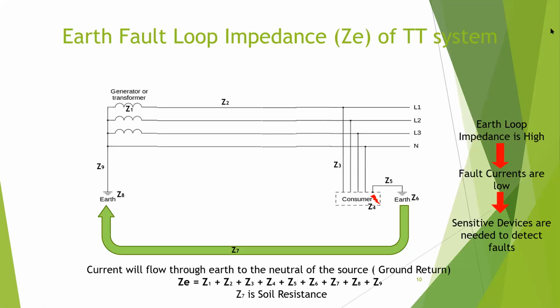Now we are going to define the earth loop impedance of the TT system. This is one of the most important things you should know. Assume you have a fault in your system. When that fault occurs, there's a path for the current to flow. The impedance or resistance of that path is called the earth loop impedance. Usually we call it an impedance because there are capacitive elements also in that path, so we can't take it as completely resistive. So we are going to define what the earth loop impedance path of the TT system is.